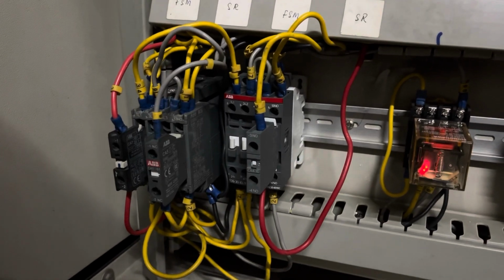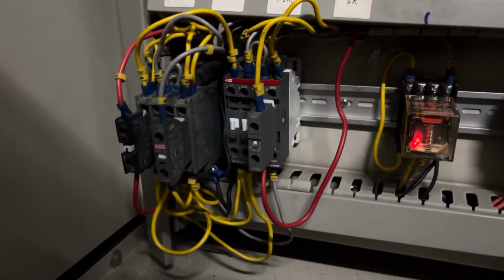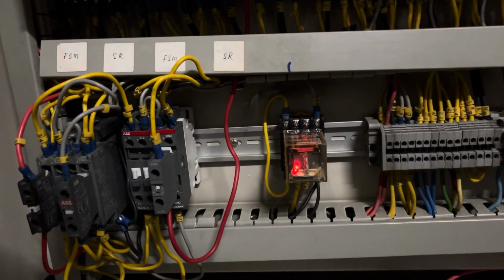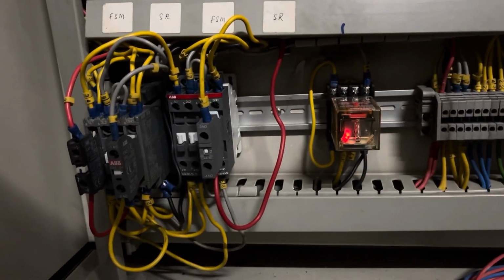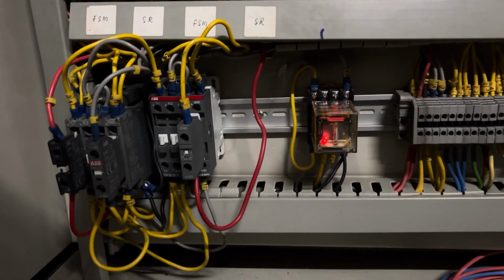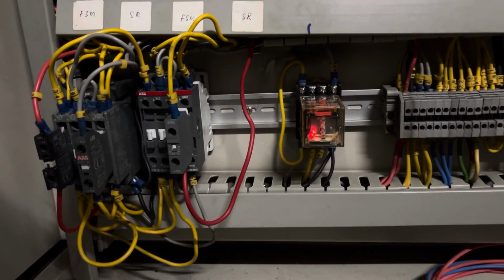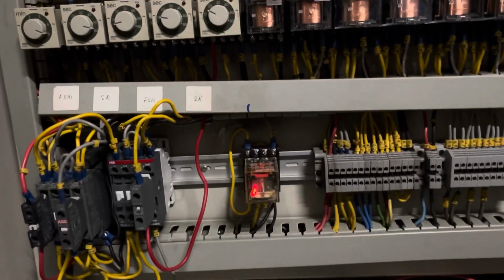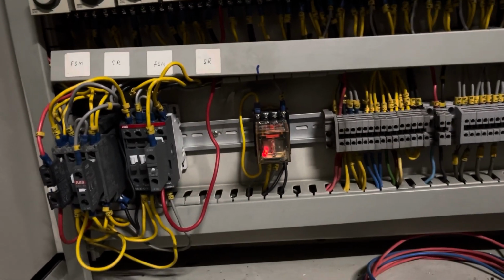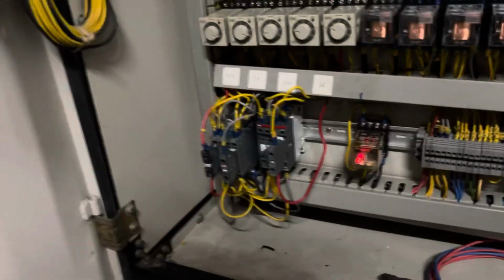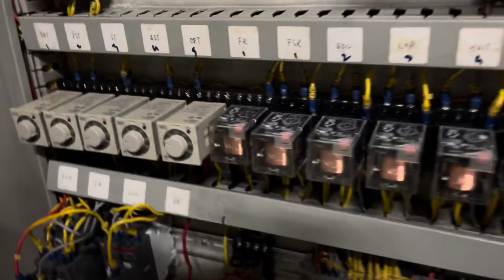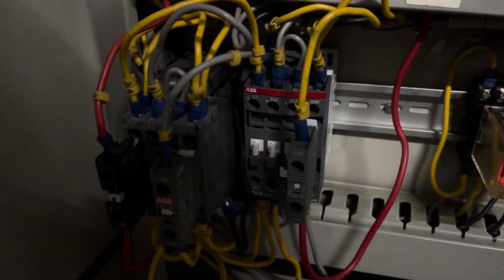The fuel solenoid master seems doesn't hold. I mean this relay. It's supposed to hold and the genset supposed to start, but it just cuts in and cuts off again. This is the fuel solenoid master and this is the start relay. The start relay doesn't hold for long, it just releases back. So it could be due to the voltage drop. Alright, let's try one more time. Voltage weak, that's why it releases back.